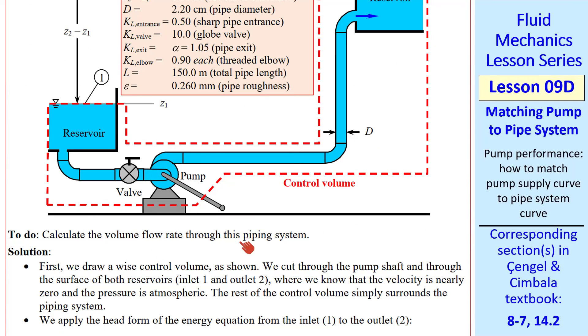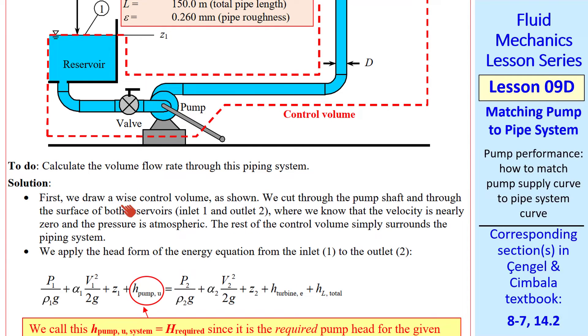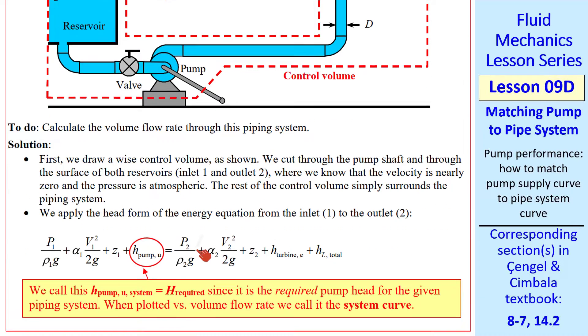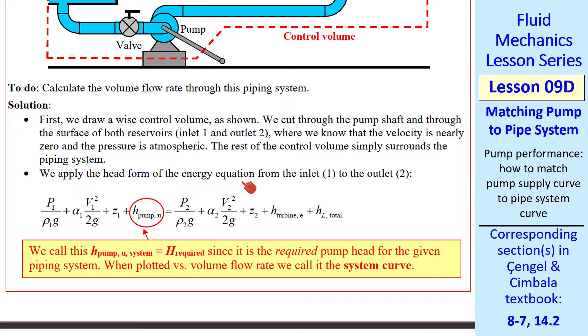We're asked to calculate the volume flow rate through this piping system. I already talked about our wise control volume. And then we apply our workhorse head form of the energy equation, which is shown here. By wise choice of control volume, P1 and P2 are both atmospheric. V1 is approximately zero at the surface of that reservoir, as is V2. There's no turbine in this problem. So we're left with H pump U, elevation difference, and the total irreversible head loss. Since we're doing an equation for the system, this H pump U is H pump U system, which we can also call H required.